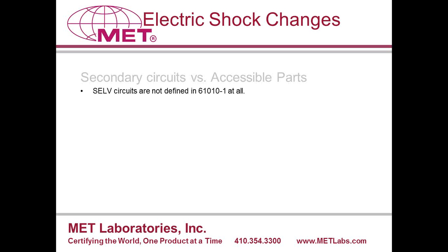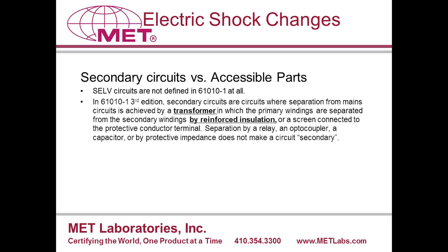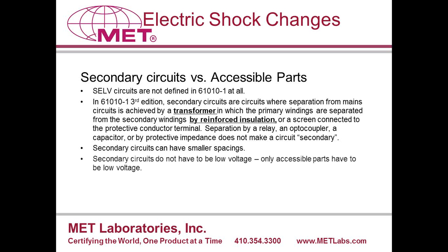I'd like to make note of an interesting definition in 61010-1. If you're familiar with 60950-1, you may have heard the term SELV, or Safety Extra Low Voltage Circuit. This is not defined in 61010-1. Instead, 61010-1 uses the terms secondary circuit and accessible part. They're not the same. A secondary circuit is only a circuit which is separated from mains by an isolating transformer with reinforced insulation or a protective grounded screen. Because the transformer protects secondary from transients, secondary circuits can have lower creepages, clearances, solid insulation thicknesses, and dielectric strength values. A secondary circuit is not necessarily low voltage and does not have to be.